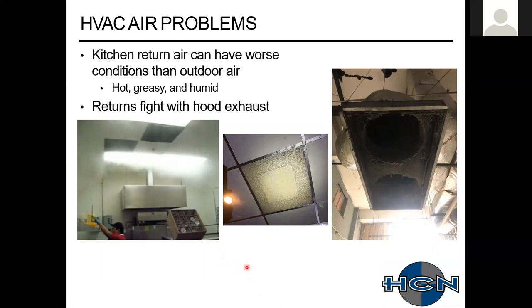So here are a couple of pictures of some returns in spaces. Depending on how large that rooftop unit is, your return sometimes can be a larger exhaust than your hood itself. So those two systems could be detrimental to each other, especially if you have the return located too close to the hood. I think typically most of the major manufacturers would say 10 feet away. I usually tell people to keep the return as far away from the hood as possible.